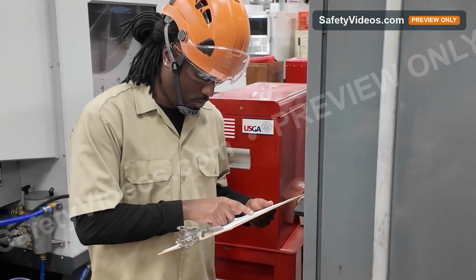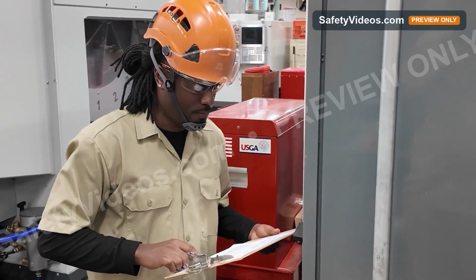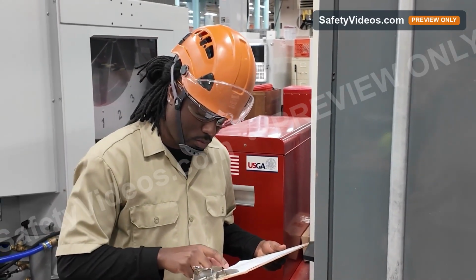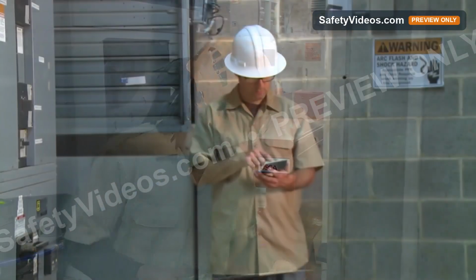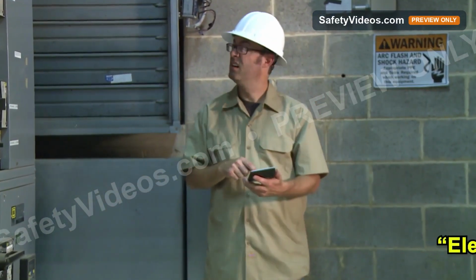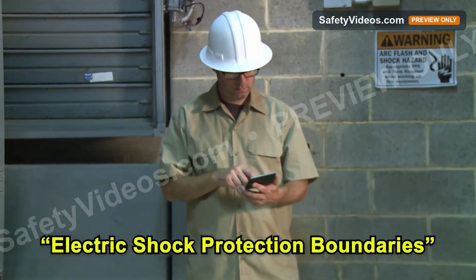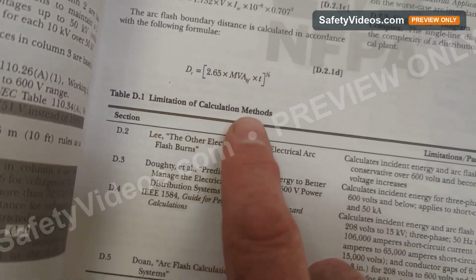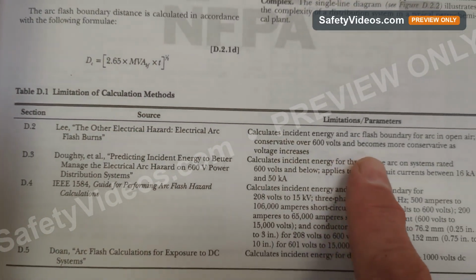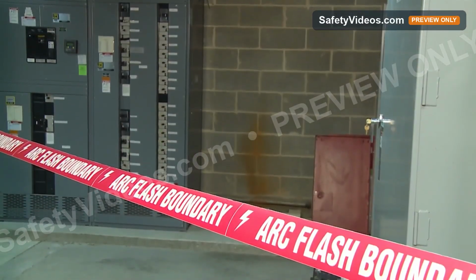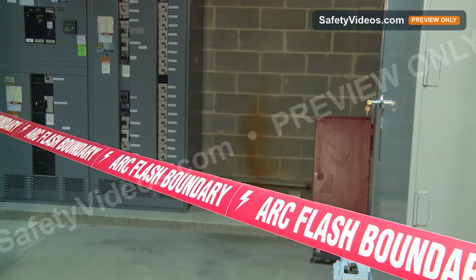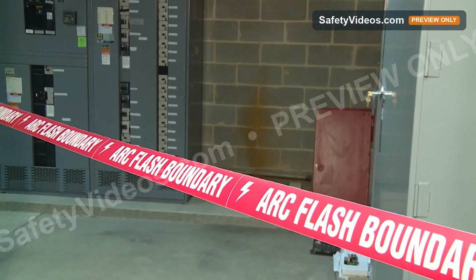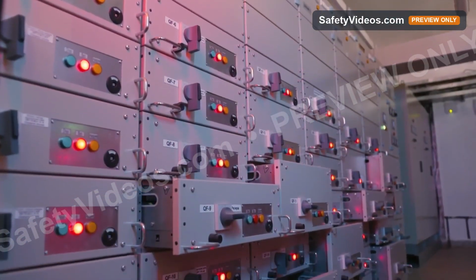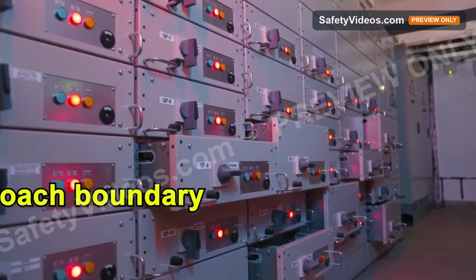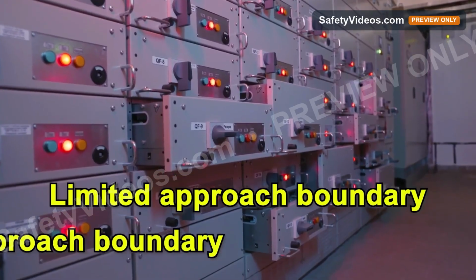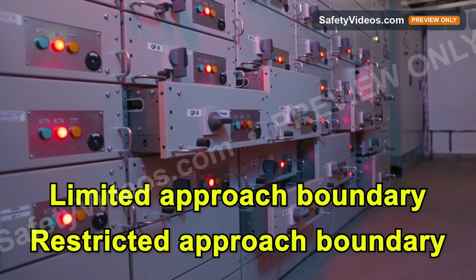You should also consider the design of the equipment that you're working on and how well it has been maintained. These factors can help you calculate the electric shock protection boundaries using the table that the NFPA 70E standard provides. These boundaries should be marked using signs or other visual indicators. There are two types of electric shock protection boundaries: the limited approach boundary and the restricted approach boundary.